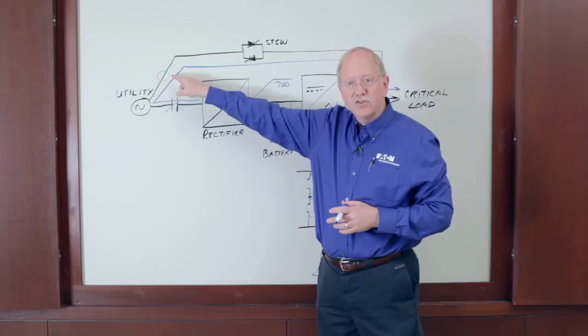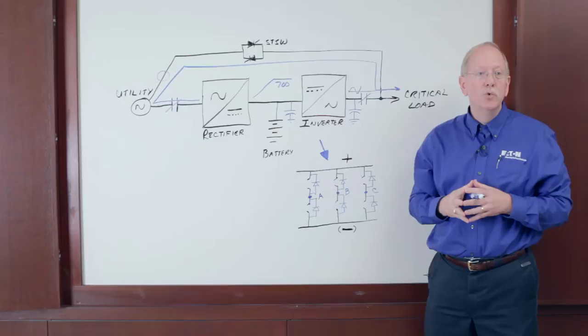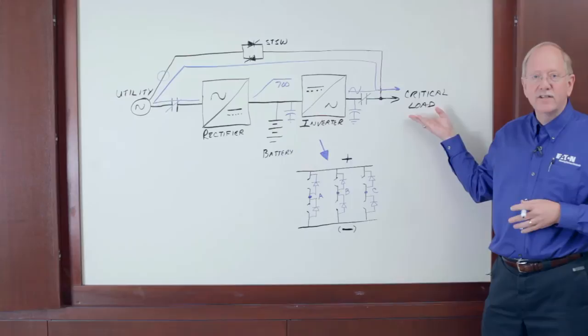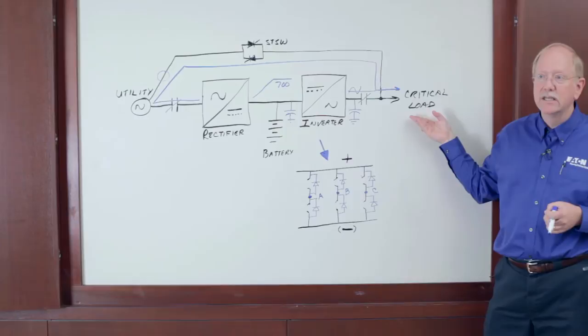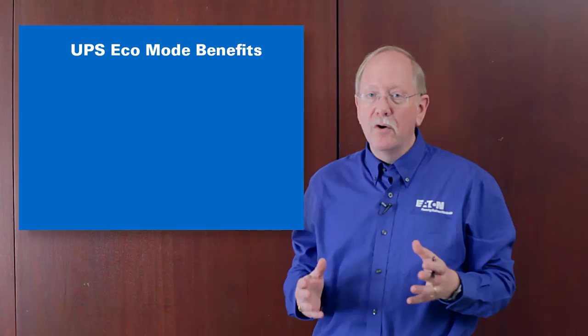So, in eco mode, I'll have power through the static switch. If the incoming power becomes disturbed, I can flash on the rectifier and the inverter, and I can do that in as little as two milliseconds, including turning off the static switch. Is that fast enough for the critical devices that we're supporting here? Well, the guidelines say any transition should be less than 20 milliseconds. The reality is, the faster the better.